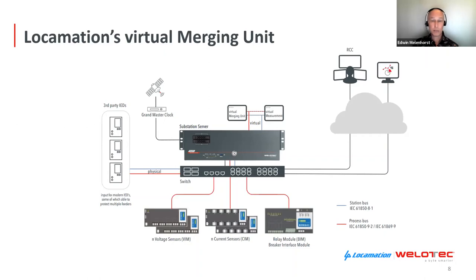You also see a BIM, breaker interface module. This interface module has several digital I/O for controlling breakers and monitoring breaker positions and other digital I/O. The next version of this product will also be based on IEC 61850, using GOOSE messaging.